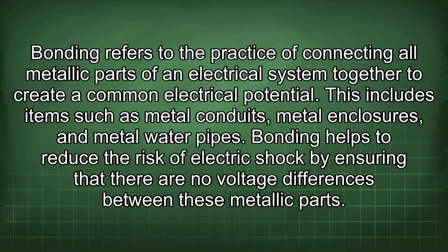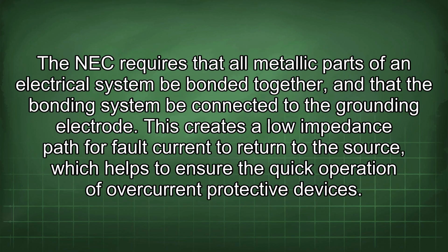Bonding helps to reduce the risk of electric shock by ensuring that there are no voltage differences between these metallic parts. The NEC requires that all metallic parts of an electrical system be bonded together, and that the bonding system be connected to the grounding electrode. This creates a low impedance path for fault current to return to the source, which helps to ensure the quick operation of overcurrent protective devices.